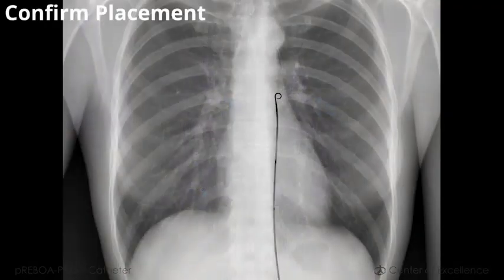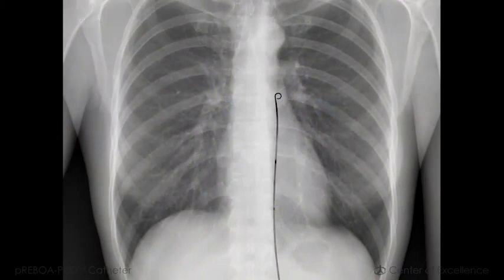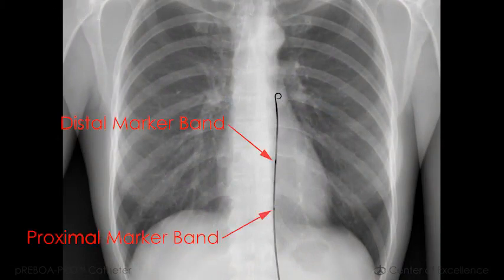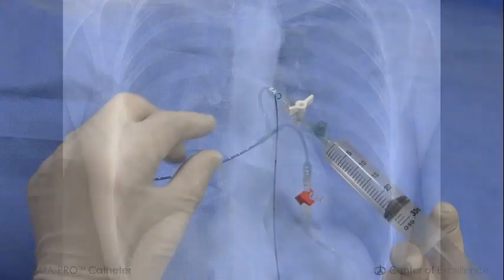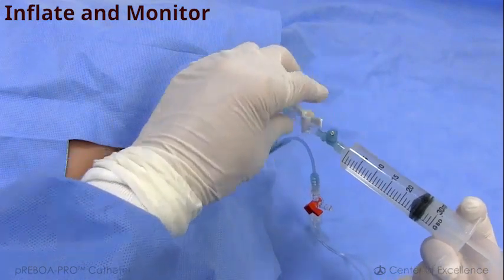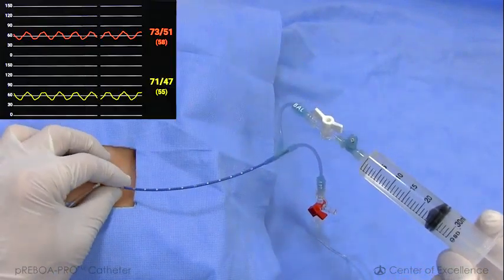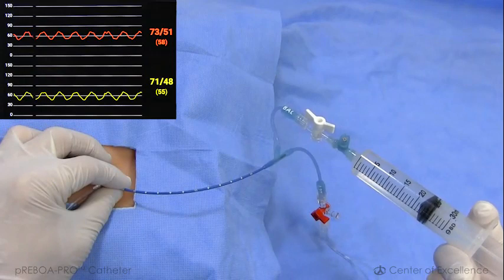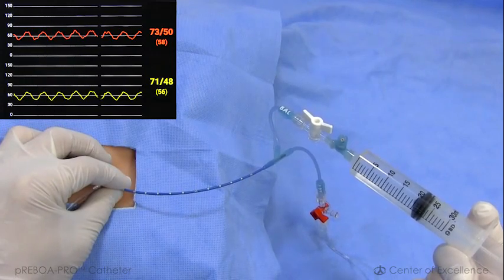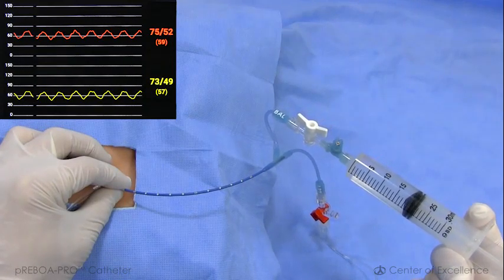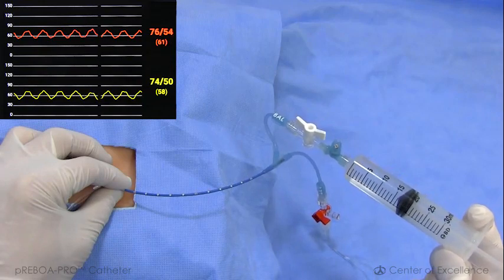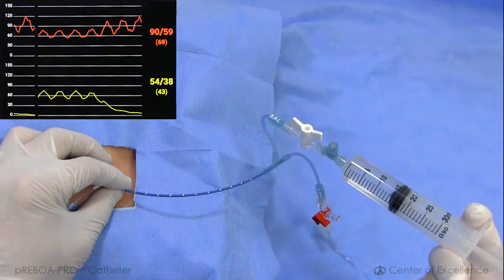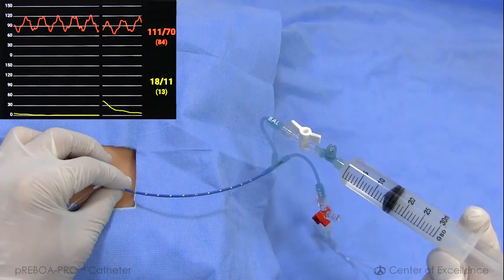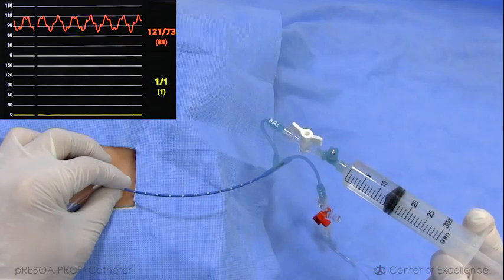If available, use X-ray or fluoroscopy to confirm placement. Radiopaque marker bands are located at each end of the balloon to identify the balloon's location. Slowly inflate the balloon to occlusion while monitoring the patient's blood pressure for signs of an increase in pressure above the balloon or loss of pulsatility below the balloon. The built-in safety valve is designed to only open if the balloon is inflated too quickly and help prevent overinflation.